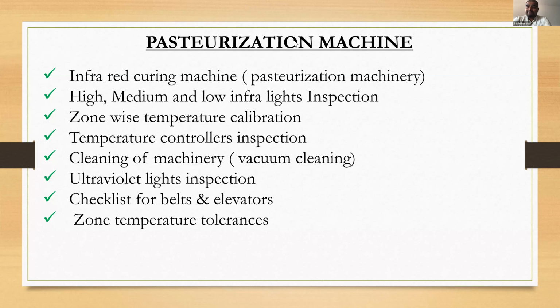Zone-wise temperature calibration - we have to continuously monitor which zone has what temperature. There are 5 zones. In all zones we have to continuously check what is the set value and what is the present value. But it's inbuilt in the machine itself - if the present value is beyond tolerance, the machine will stop by itself, so no need to worry about that. But we still have to continuously monitor using this temperature gun.